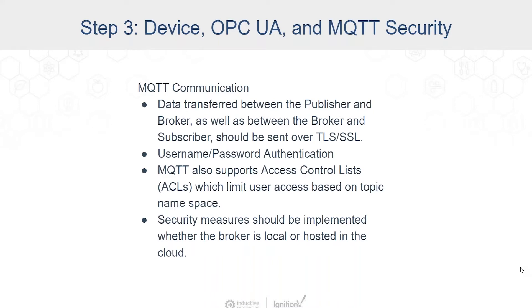We have entire webinars dedicated to this topic. Essentially, MQTT transfers data from a transmitter — a publisher — up to a broker, and then any application can subscribe to that broker. You have publisher to broker and broker to subscriber, and all of that should be sent over TLS/SSL. MQTT also supports username and password authentication, as well as access control lists (ACLs), which limit user access based on a topic namespace. One of the great things about MQTT is that it can be hosted in the cloud, but certainly security measures should be implemented whether it's local or in the cloud.